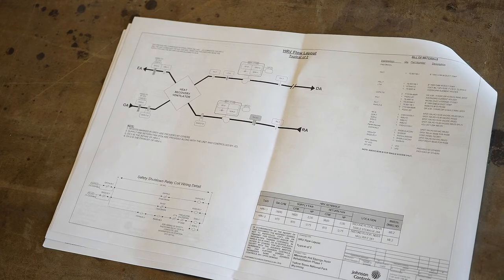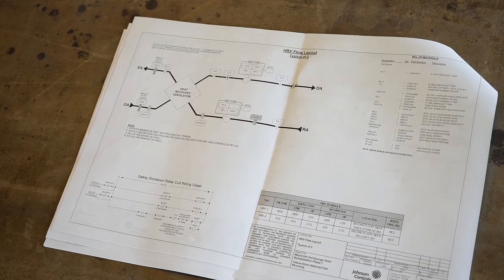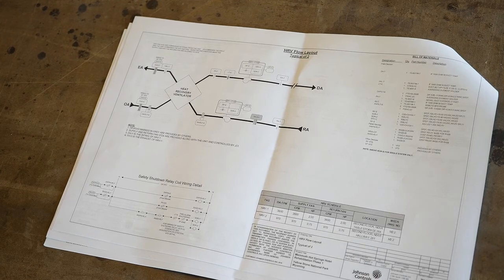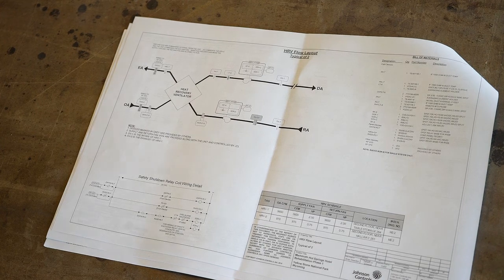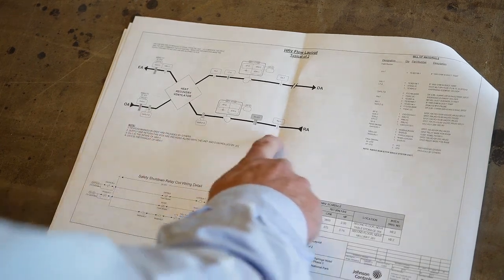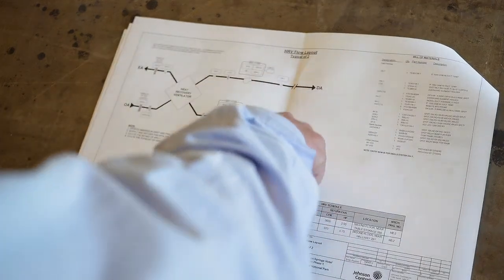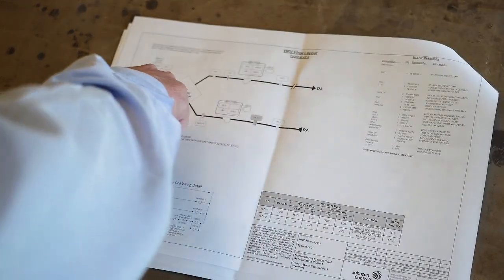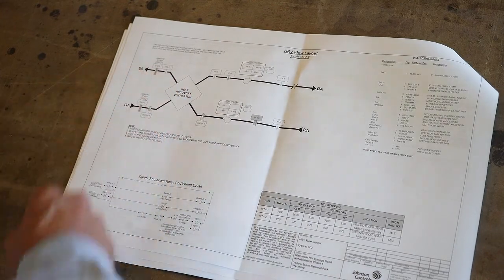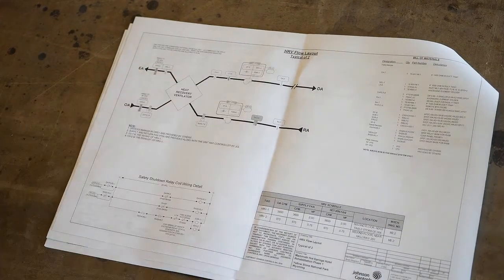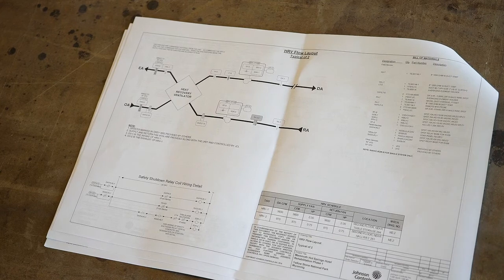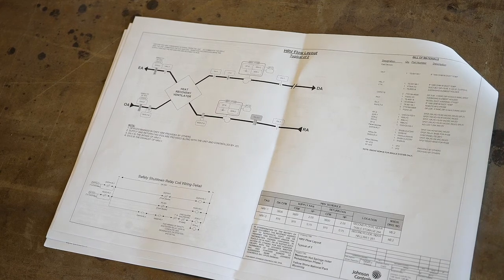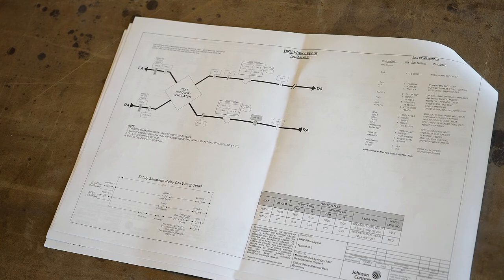Right. See, the one up in this attic, I thought he only showed one set of filters, so I wanted to make sure you guys knew there was another set of filters up there on the other side. Okay, and then we have temperature sensors located on the return air, the discharge air, the exhaust leaving the heat exchanger, and preheat temperatures. So you have different temperature sensors on the front end, so if somebody ever wants to do calculations to see what it's doing for heat recovery and efficiency, you can do that also.